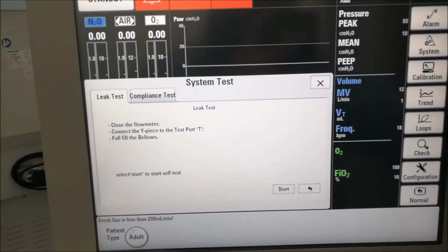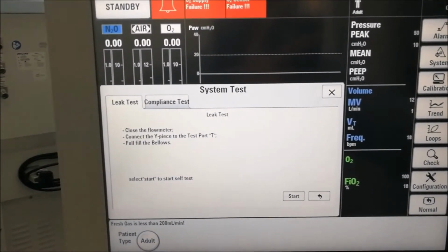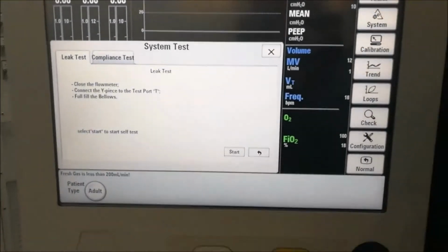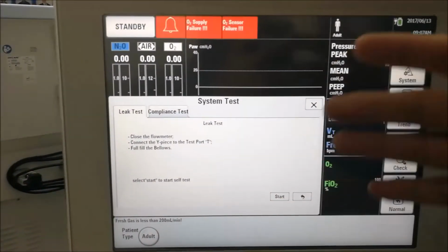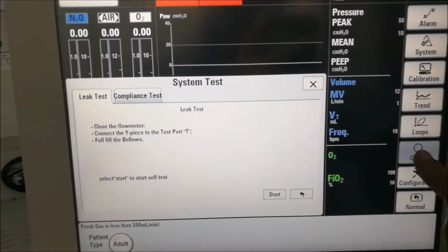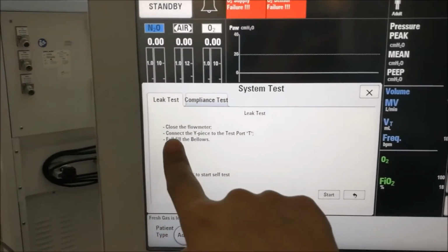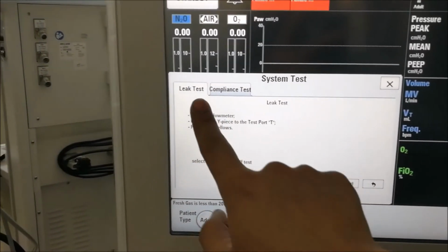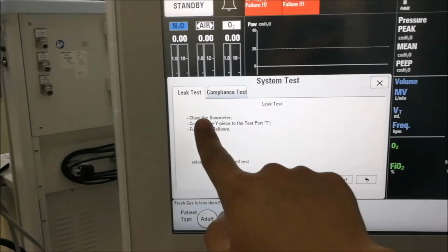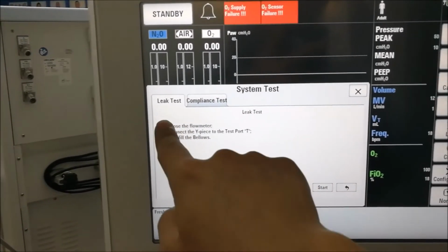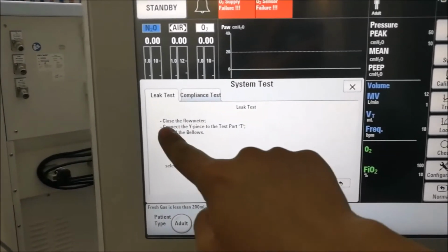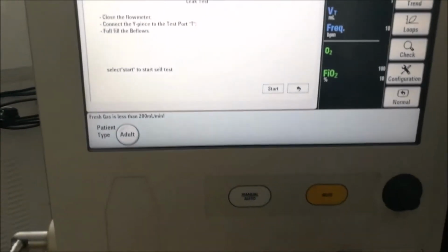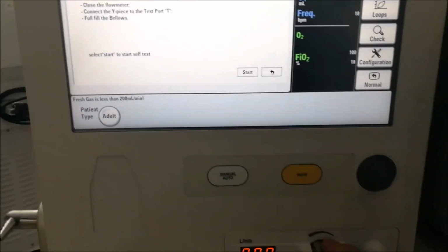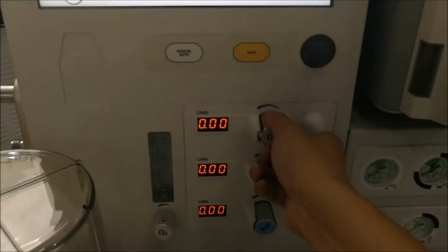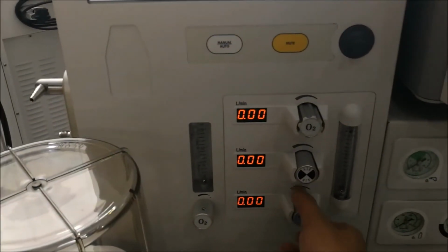Okay, about the check. The check is something the doctor does every day when opening the machine. First is the leakage test. When we do the leakage test, we can do it step by step. First, close the flow meter. We need to make sure all the flow meters are closed.